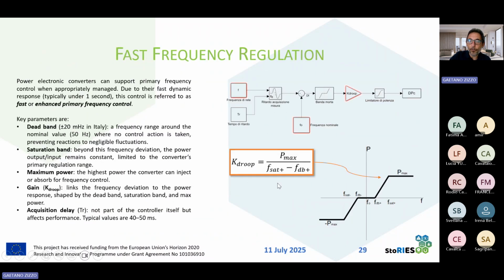implemented. And from this formula, having set the dead band and the saturation band, identify the frequency saturation band, identify the maximum value of the frequency after which the power from the storage is equal to the maximum allowed, we can calculate Pmax.